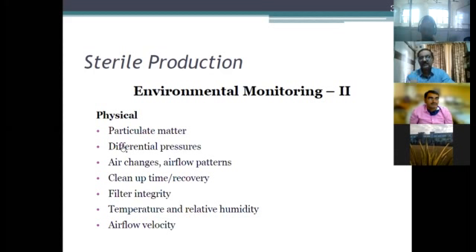As per the guidances and regulatory requirements, a differential pressure of not less than 15 pascals is required. This is the standard. So your pressure cascade has to be maintained like this. Then only your contamination levels will be controlled. Otherwise, there is every chance that contamination may enter the product because it's an aseptically filled product. So these are all risks.